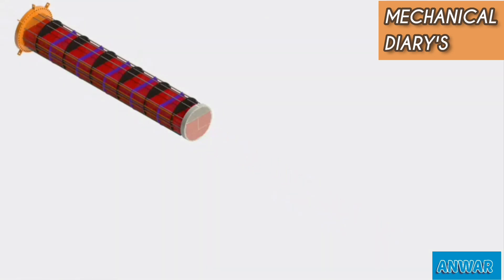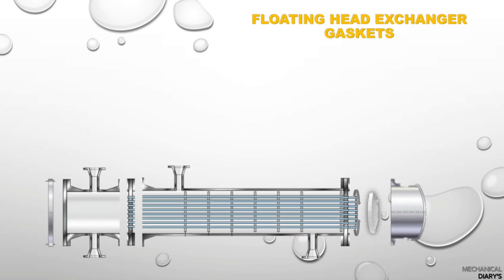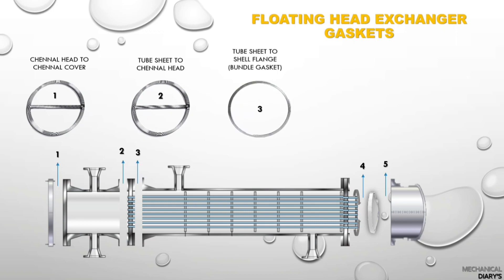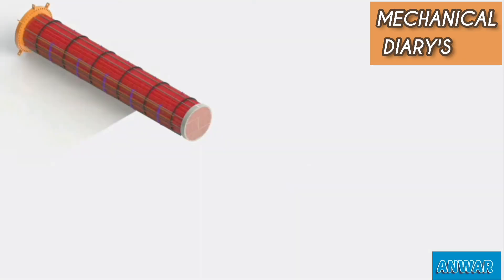One of the most common and very important questions is about floating head exchanger gaskets. Floating head exchangers always have five types of gasket. In this video you will know the five gasket names and where each is placed. First gasket: channel head to channel cover. Second: tube sheet to channel head. Third: tube sheet to shell flange. Fourth: floating head gasket. Fifth: shell back cover gasket.